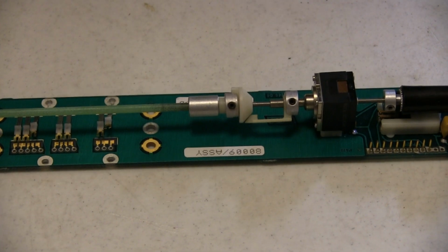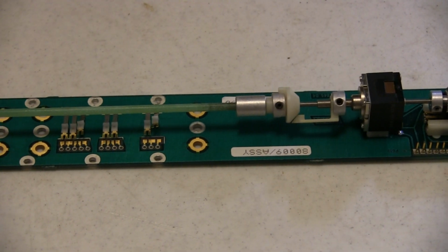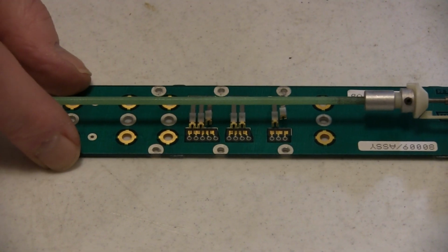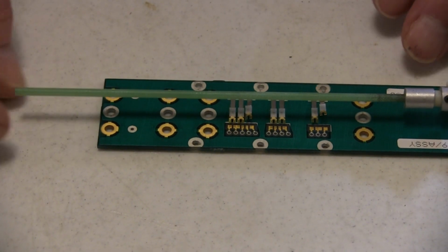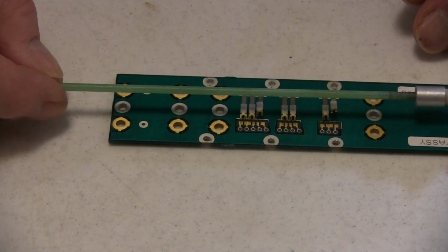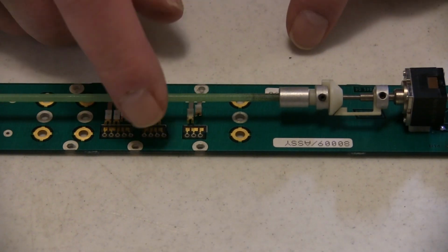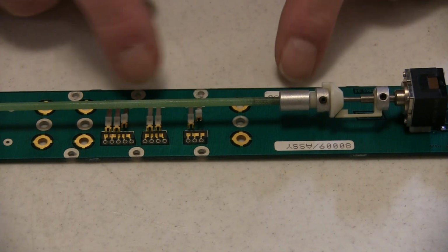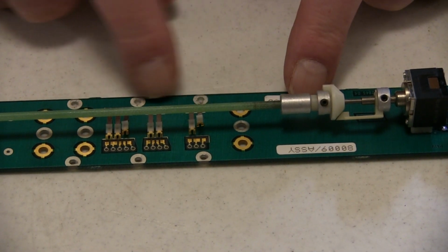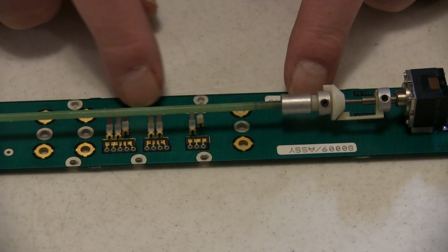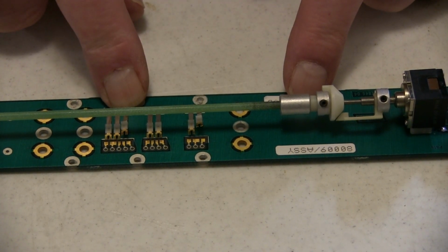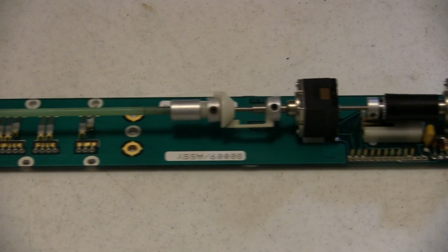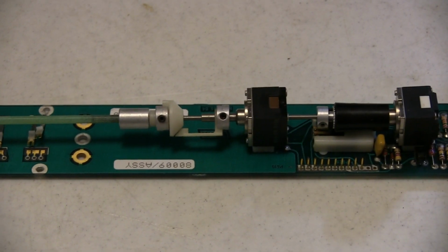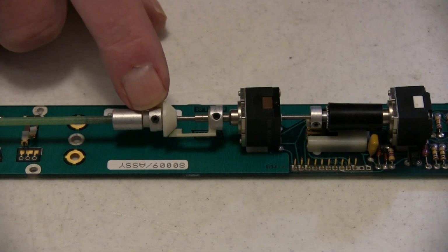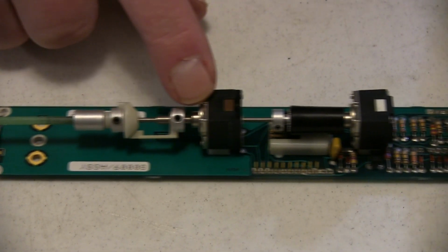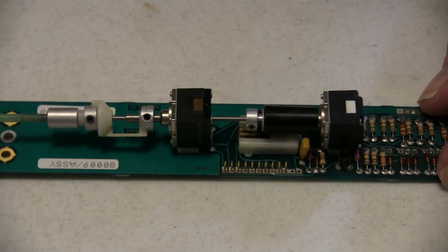I've removed the upper board or the outer board so that you can see the mechanism that is involved in calibration and variable gain setting. This is the shaft that goes out to the variable knob, and right here would be, I've taken it off, but it would be the cam for the attenuator, and also these switches on this board are the ones that set the readout levels.